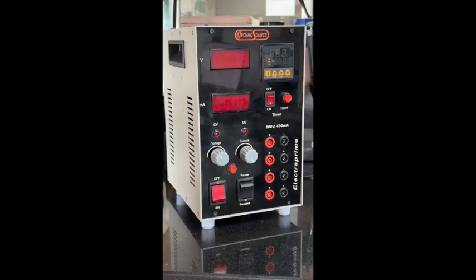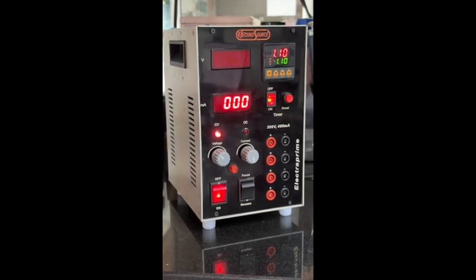Indication 2. Instrument is on but no display is on. If the mains switch light is on and the light on CV or CC indicator is on, but both or one of the displays are off, this means that the power to the displays has been cut due to a defective circuit or defective wiring, or that the display has developed a problem. Please contact us to have this issue resolved.